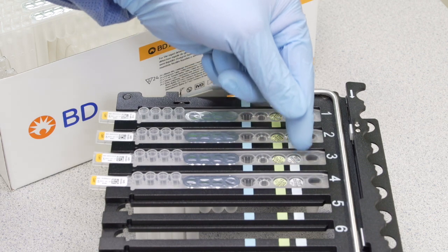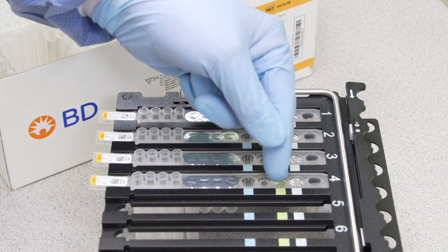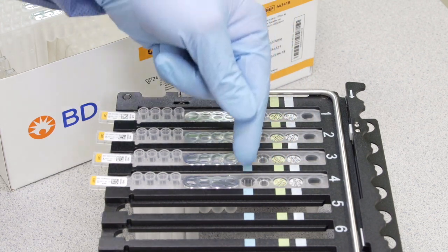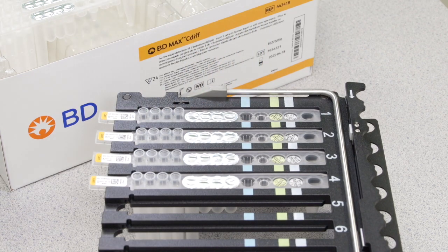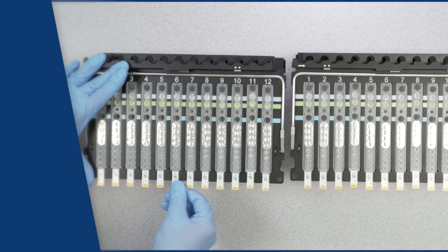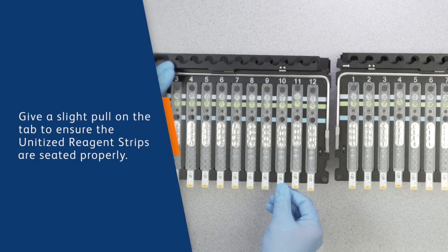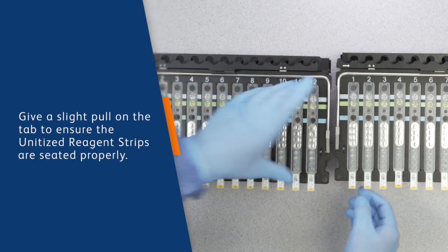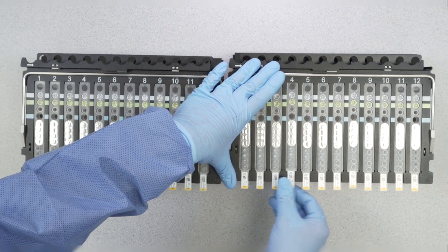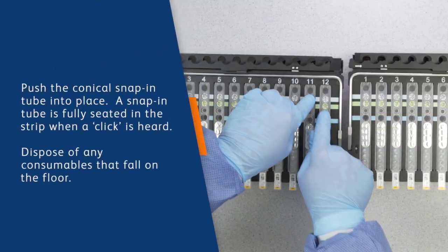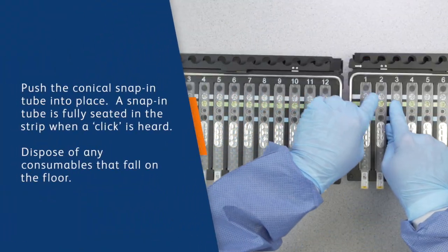The white stripe lines up with the extraction tube, the green stripe with master mix 1, and the blue stripe with master mix 2. The assays without a master mix 2 will have an open hole. Now you can see your unitized reagent strips are all secured into place. Your extraction and master mix snap-ins are seated properly.